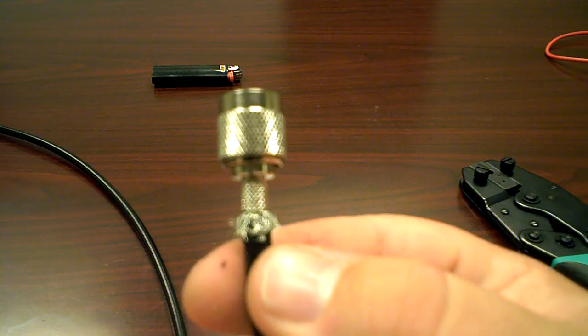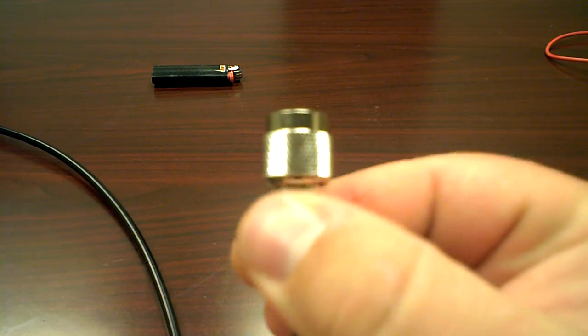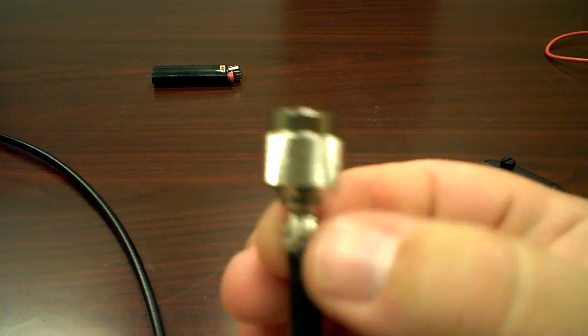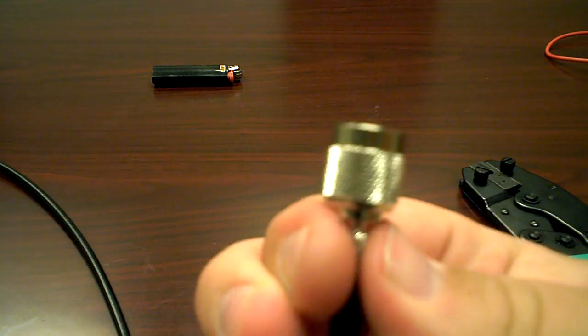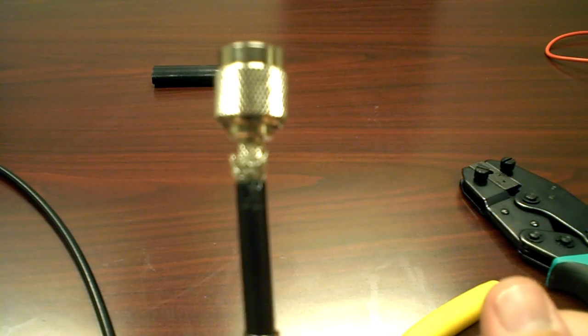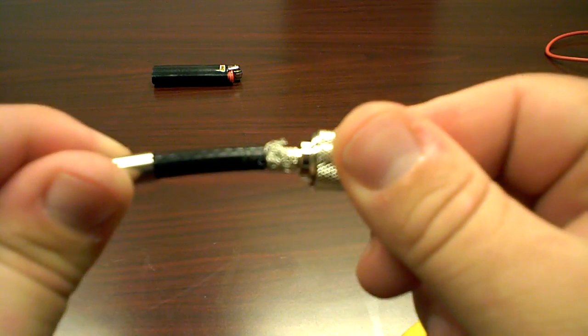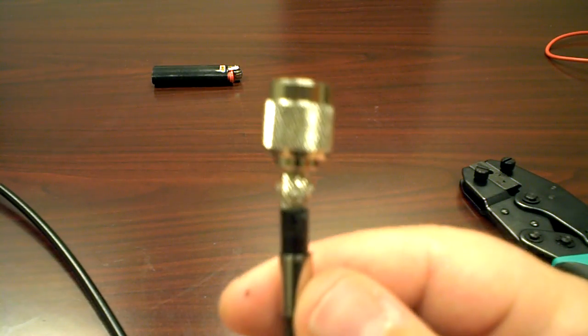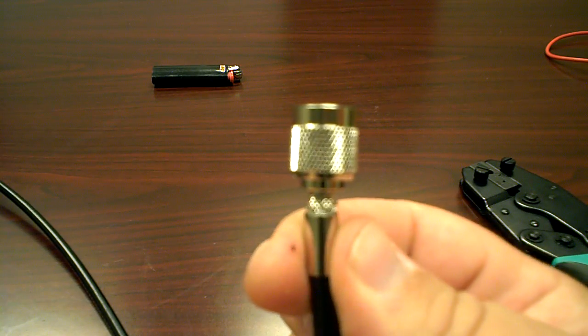So at that point you'll basically take your braid, fold your braid back up the bottom of the connector all the way around. That's just going to ensure that we've got a really good ground. So I'll turn that sideways, you see. I'm going to slide the metal ring up, making sure that's down real good.